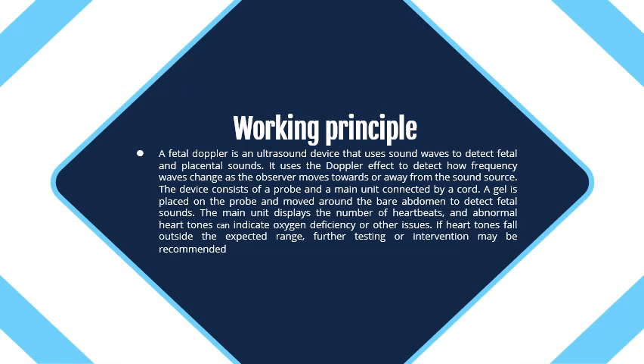Moving on to the working principle: a fetal Doppler is an ultrasound device that uses sound waves to detect fetal sounds. It uses the Doppler effect to detect how frequency waves change as the observer moves towards or away from the sound source. The device consists of a probe and a main unit connected by a cord. A gel is placed on the probe and moved around the bare abdomen to detect fetal sounds. The main unit displays the number of heartbeats, and abnormal heart tones can indicate oxygen deficiency or other issues. If heart tones fall outside the expected range, further testing or intervention may be recommended.